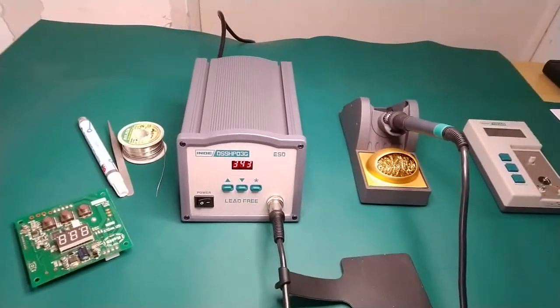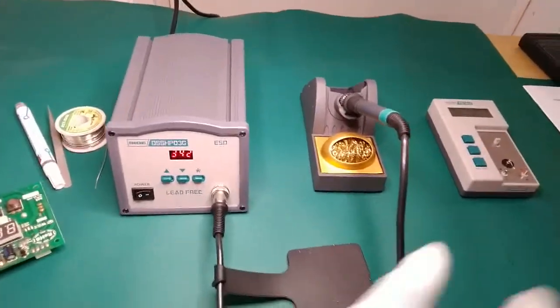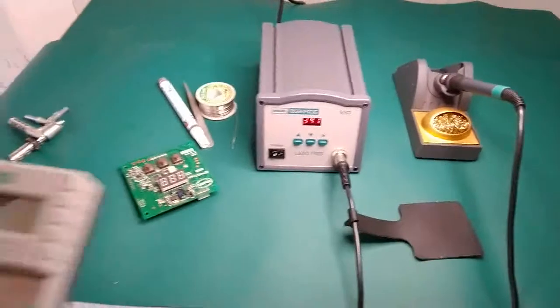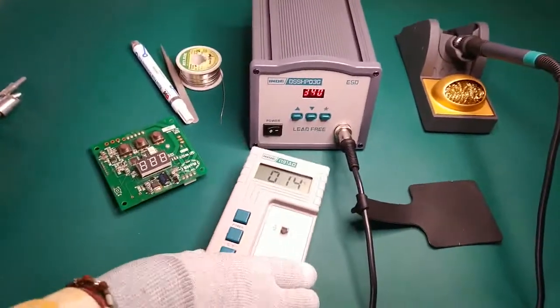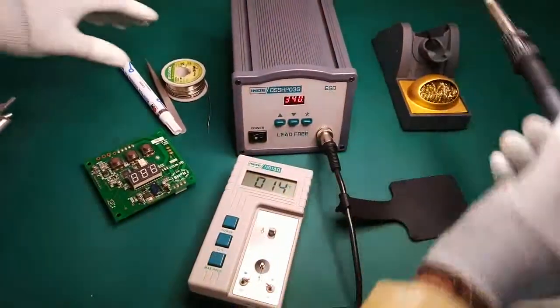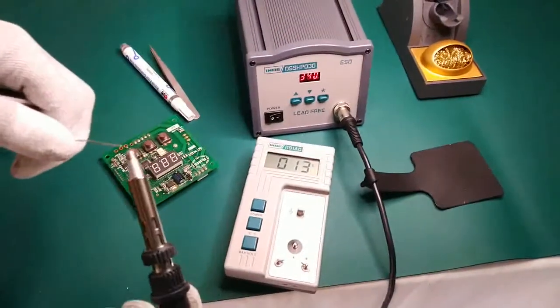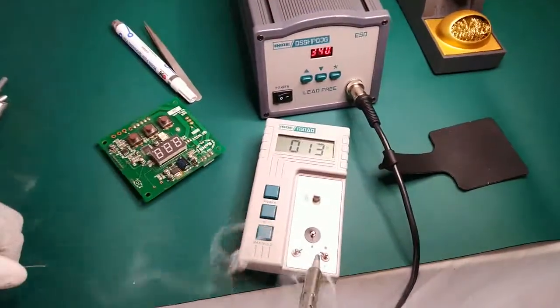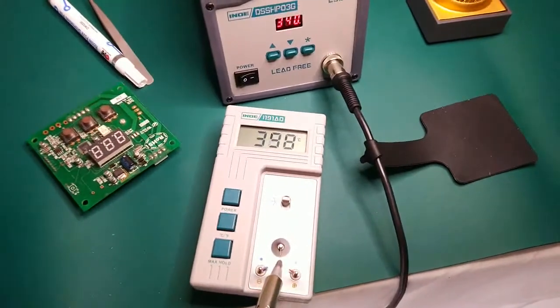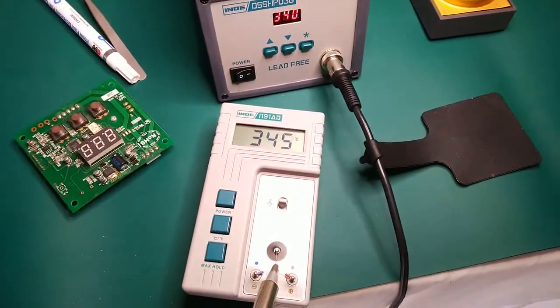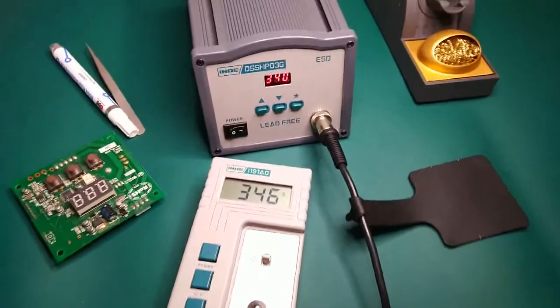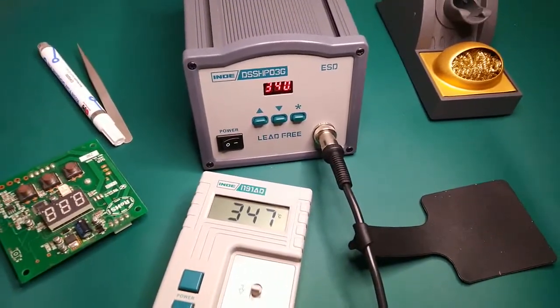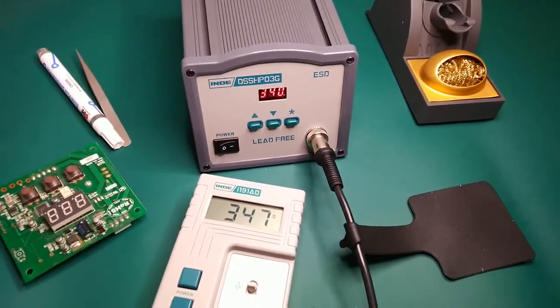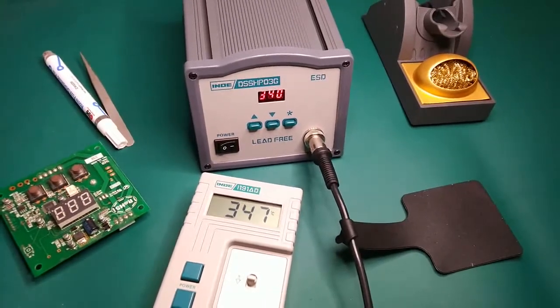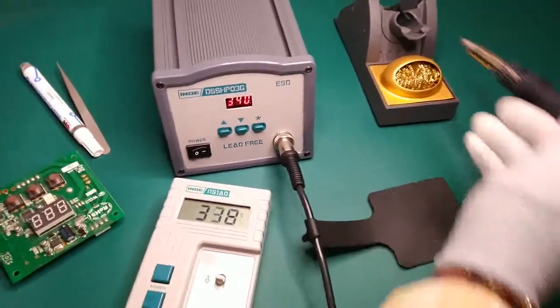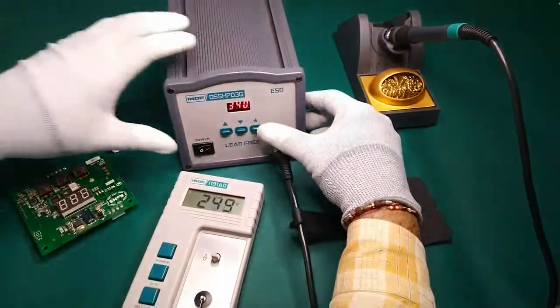Now we will show you how to calibrate this instrument if the set and actual temperatures are different. We will use an external thermometer for calibrating. First we will measure the actual temperature by touching the thermocouple provided on the top of this thermometer. Here we can see the set temperature is 340, but the actual temperature observed on the thermometer is 347.